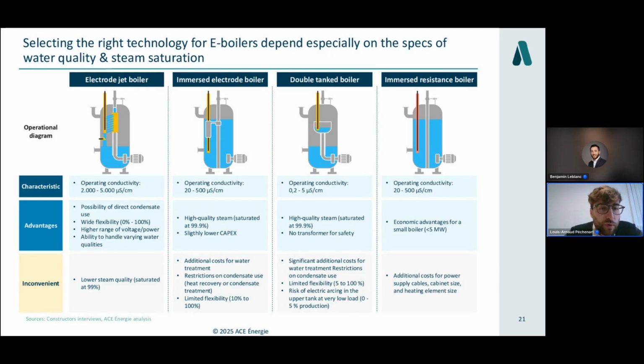You will adjust the level of production of steam with the level of water inside the reservoir. You have different ways to do that. You can use a pump to adjust the level, or mask some holes to reduce the number of holes that are producing jets. For the immersed electrode boiler, you have the 3 electrodes inside the boiler that are directly immersed, and the electricity will pass from the electrode through the water to the boiler tank, which is usually neutral, and that way you will have electricity passing through water and producing heat once again. To adjust the level of production here, you adjust this mask that will mask a part of the electrode.